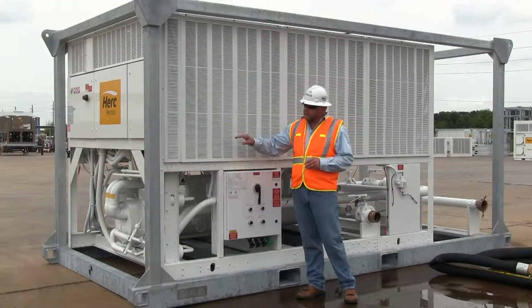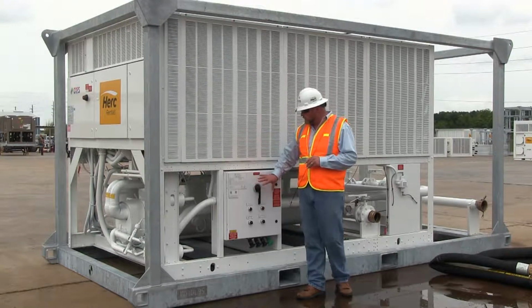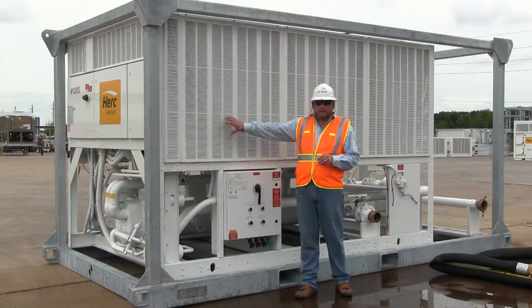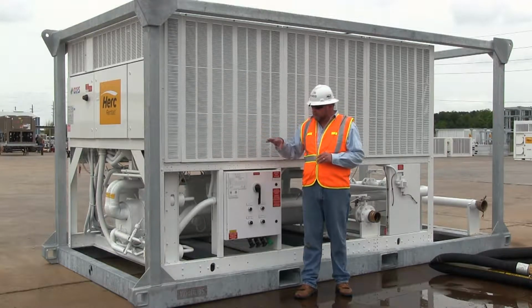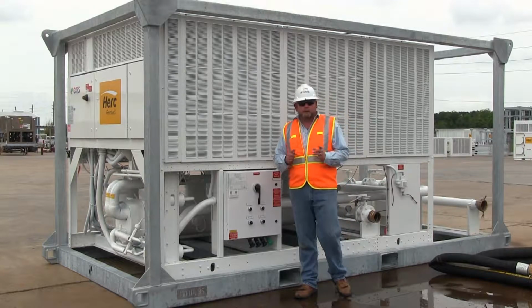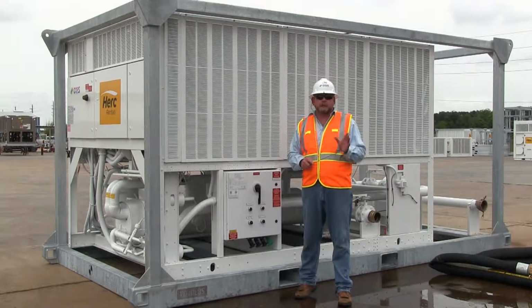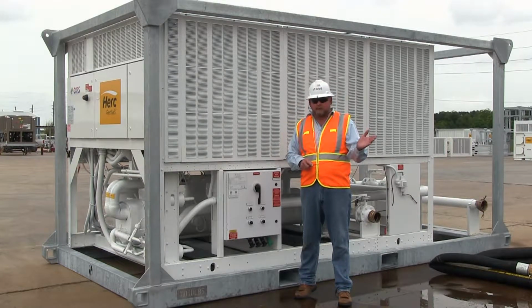Please note that all the CAPS built equipment has integrated breakers for both the pumps and the chiller itself. So we've got all the short circuit and overload protection contained within our package. When you hook up to your main power supply, you just need to make sure you're protecting your cable, be it through a generator breaker or through the main house power.